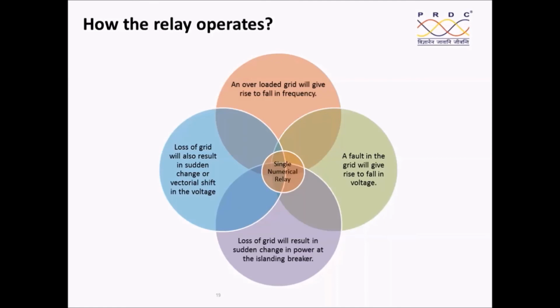Therefore, you can have a single numerical relay or a set of relays by which islanding can happen. An overloaded grid will give rise to a fall in the frequency. Therefore, if there is a prolonged under frequency, we can have the islanding. A fault in the grid will give rise to a fall in the voltage. Therefore, even that we can use to ensure islanding.